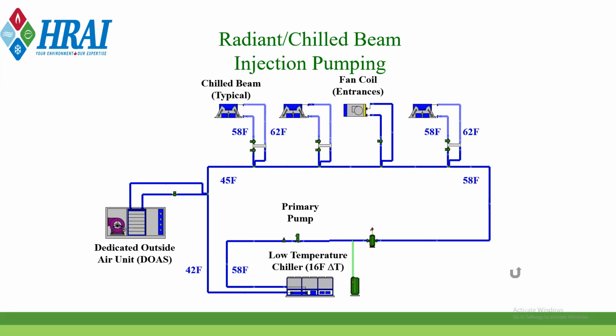And here's why. There's one pump in this example that circulates the water through this loop. At each of these zones, there is a form of hydraulic isolation, which is right here. Those are a hydraulic separator that could be achieved through perhaps two closely spaced T's. That gives you that hydraulic isolation, or there are engineered fittings available that essentially achieve the same thing, but with fewer connections. And then running that lower fluid temperature throughout the building to deal with some of the condensation challenges that you might be faced with.